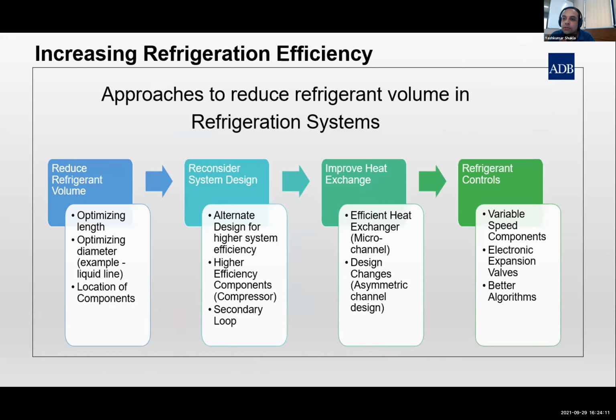Now let me shift to how we can increase refrigeration efficiency. What approaches can reduce the refrigerant volume in a refrigeration system? Once you have decided on the capacity of the system you need in your space, you first need to think about how to reduce the refrigerant volume. You can think about optimizing the length and location of the components, and how the diameter of the refrigerant components can be reduced. You need to reconsider and re-optimize the design, asking how an alternate design can lead to higher system efficiency. Using higher efficiency components, such as oil-free compressors and variable speed compressors, can lead to a significant reduction in the refrigerant in refrigeration systems. You can also have secondary loops. You can use water or brine as the secondary loop, so you can cut down on the length of pipes of the refrigeration systems.